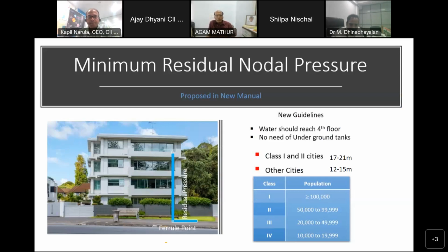Now we are coming with the residual pressure of 17 to 21-meter range in class 1 and class 2 cities. For other cities, it will be like 12 to 15 meters. For rural areas, we are coming with the 7-meter head.